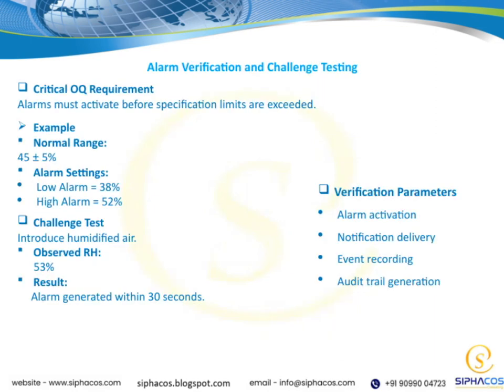Now, let's talk about verification parameters, the key checks that make sure alarms do what they're supposed to. We're looking at alarm activation, notification delivery, event recording, and audit trail generation. These aren't just boxes to tick, they're critical to operational qualification. Alarms must trigger before limits are breached. For example, if the normal range is 45 plus or minus 5%, alarms might be set at 38 and 52%. In a challenge test, humidified air raised the humidity to 53%, and the alarm sounded within 30 seconds, right on time.